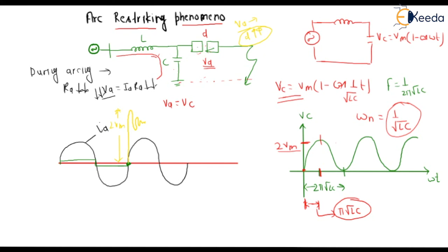So let us assume we are using our primary arc interruption at this point. When we interrupt the arc at this zero crossing point, a 2 Vm voltage will be generated. I am drawing with the yellow pen. The 2 Vm voltage will oscillate like this, and this time the same distance D keeps increasing. So a few moments later, D will be much greater after the value of 2 Vm appears across this contact of the circuit breaker. Because we know that dielectric stress is Va by D, if D is much greater, the dielectric stress will be less than the dielectric strength of the material, and the arc will be removed permanently. So this is the maximum value of 2 Vm, and to reach this maximum 2 Vm value, it will take pi under root LC time.